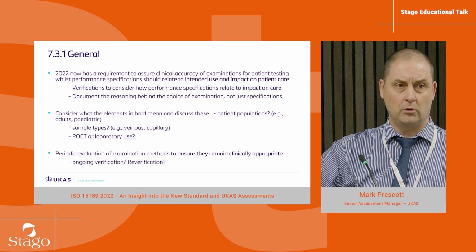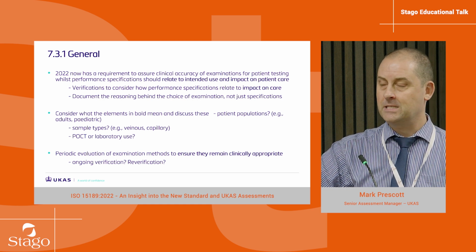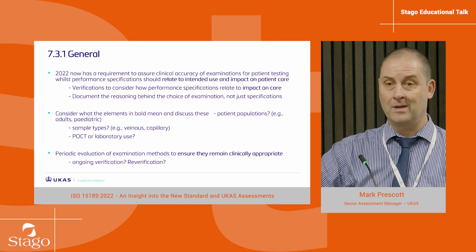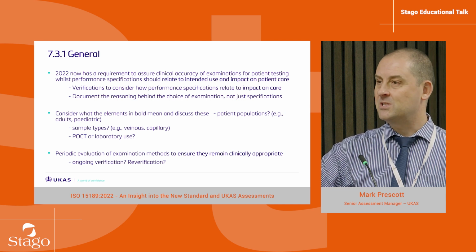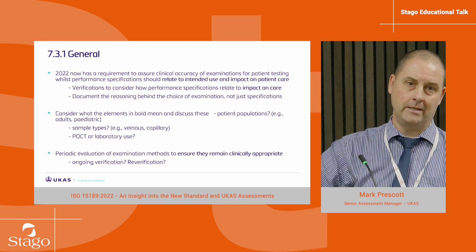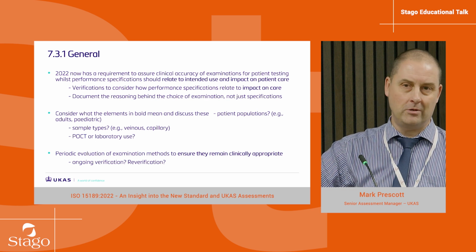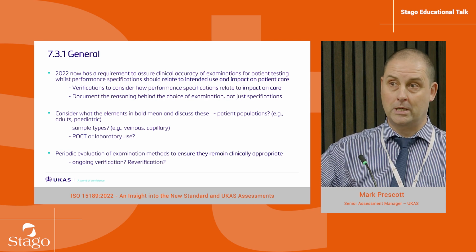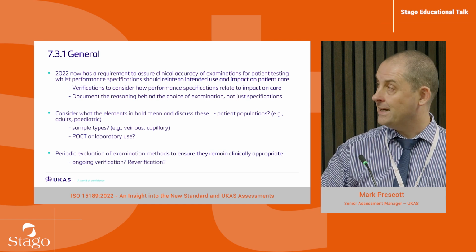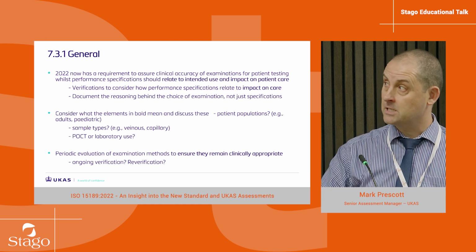It's really laboratories looking at your tests on a regular basis to see that they are doing what you want them to do after you've done your verification. It's not re-verification. You're not running samples through again and starting what you did. It's looking at your EQA, looking at your IQC. How often does it break down? Is everybody competent? And doing those things on a frequent basis just to confirm that your assays are fit for purpose.